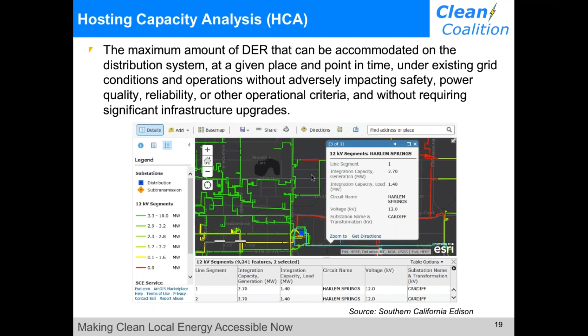So the hosting capacity analysis is essentially a snapshot in time that details how many kilowatts of DER generation and new load can be added at a specific node within the distribution grid. This is fundamental because it tells us where DER can interconnect so that it doesn't cause congestion, safety, or reliability issues. It also identifies the system limits to DER, such as thermal ratings, protection limits, power quality (including voltage), as well as safety standards. This can help project developers design the best solution, as well as guide smart grid modernization investments that will enable the grid to accommodate greater amounts of DER.